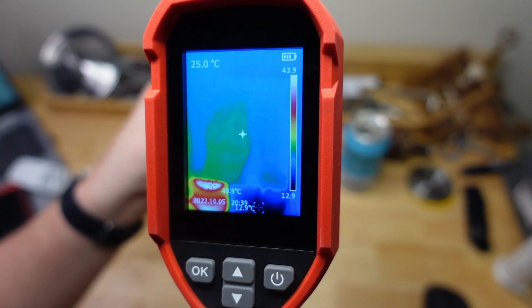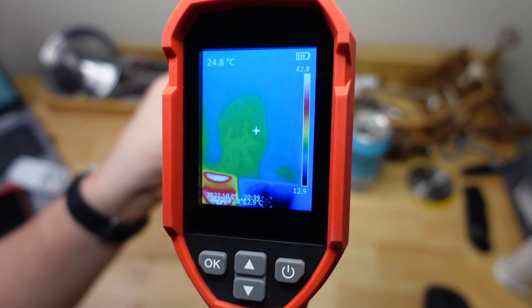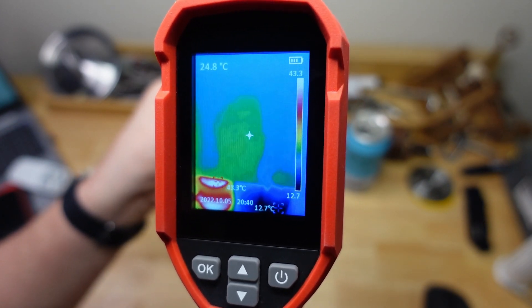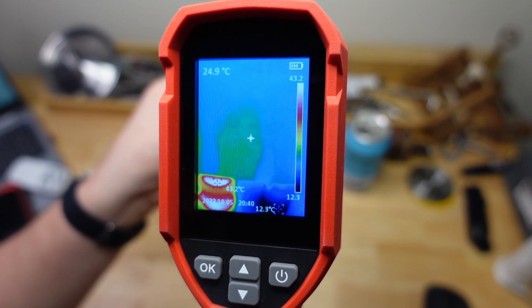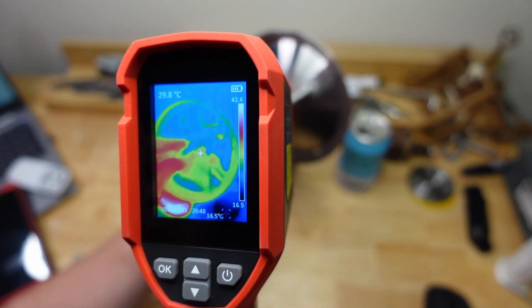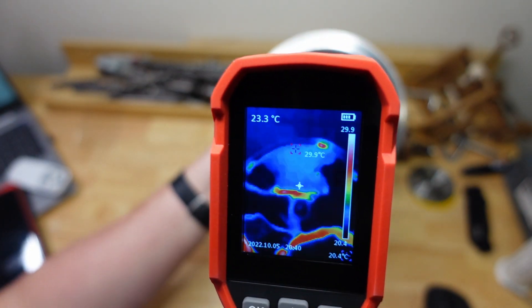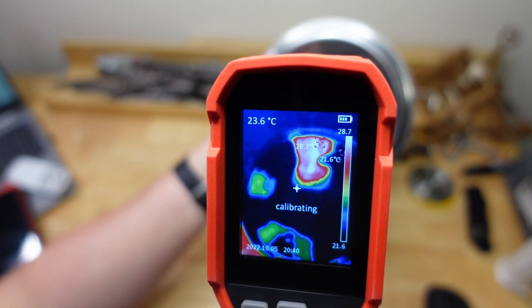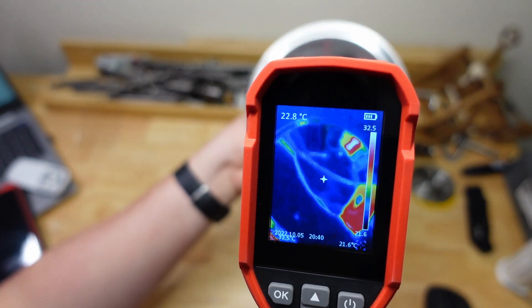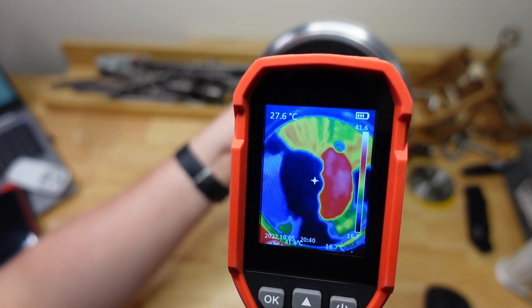And another thing you've got to watch out for is reflections. So you can actually see my reflection in the glass there. And this can be especially important when you're measuring metal. So check out this pot lid. If you want to measure the actual temperature of the metal, it helps that it's not shiny. There I am.